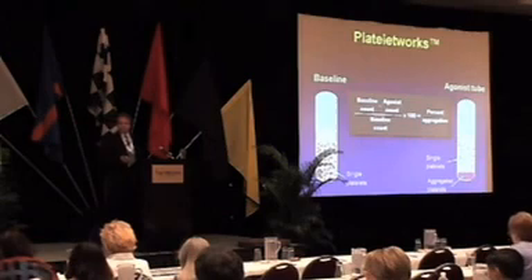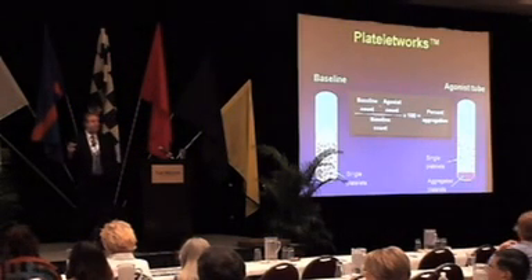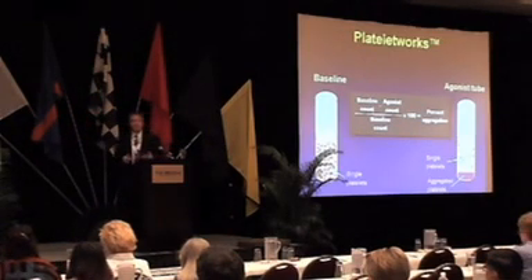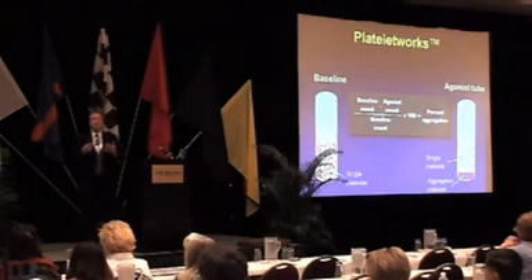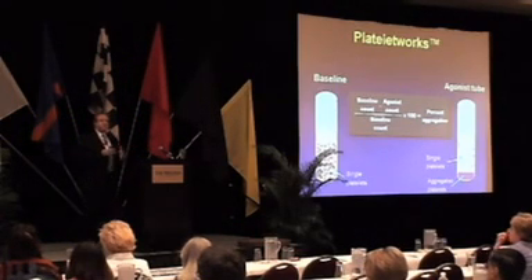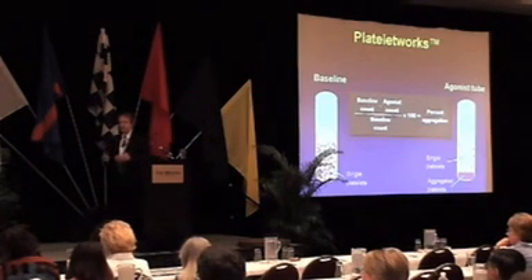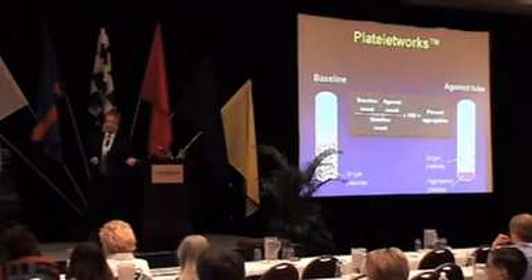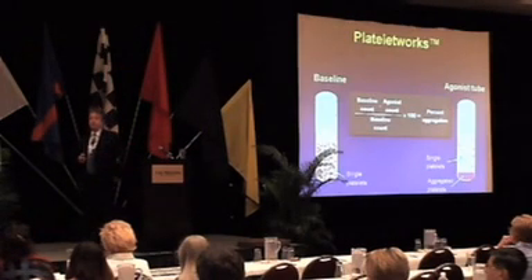The Plateletworks system works on the principle of counting single platelets. When you aggregate platelets by adding an aggregating agent, platelets form doublets and triplets. If you count the single platelets remaining at a fixed time after adding the aggregating agent, you get a mirror image of the aggregation curve. Developed originally by Dr. Stan Heptonstall and colleagues in England, it's a very sensitive way of looking for anti-platelet effects.